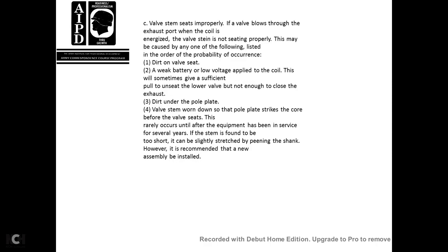Valve stem seats are improper. The valve blows through the exhaust port when the coil is energized. The valve stem is not seating properly. This may be caused by any one of the following, listed in order of probability of occurrence. 1. Dirt on the valve seat. 2. A weak battery, giving a low voltage applied to the coil. This will sometimes give a sufficient pull to unseat the lower valve, but not enough to close the exhaust.